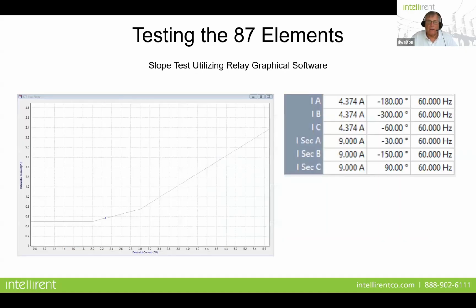Now, to verify the slope setting, basically we can go to our metering screen right here, which is really nice on the Beckwith relay, and they have the same, I believe, in the Schweitzer, and just start to increase one of the phases until we get to this intersection right here and see the relay trip. So it'll plot it right on this line. Okay, so we want to check the slope, both the 25% and the 60% slope, to make sure, and then you can calculate the delta between the 2 windings to validate that the slope is set properly.